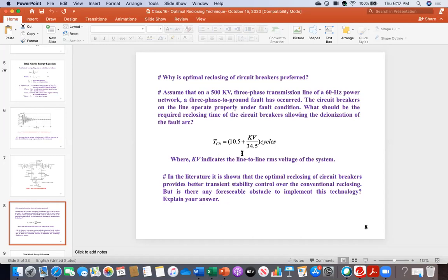This means that we have to wait at least that time. That is the question: what should be the required reclosing time? We'll be telling that the required reclosing time should be greater than that TCB value, which is 0.417 second. You must wait even a little bit more, like one more cycle. Like you all got 25 cycles, you can reclose at 26 cycles. That is the meaning of this.